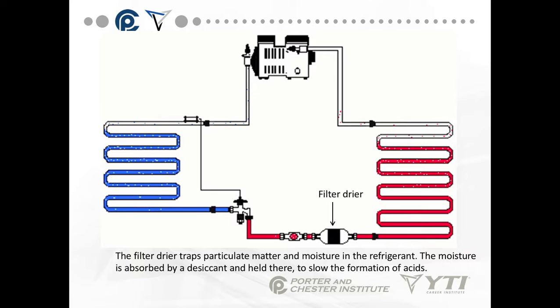Most often before the sight glass, we have a filter dryer. A filter dryer is found in most systems but it's not required. It will trap particulate matter and moisture. The moisture is absorbed by a desiccant and held there to slow the formation of acids. Any time a system is opened to the air and the refrigerant is recovered and replaced, you need to change that filter dryer — it will save your compressor in the long run.